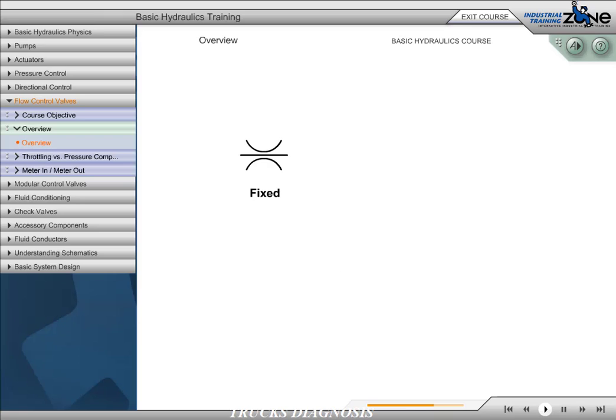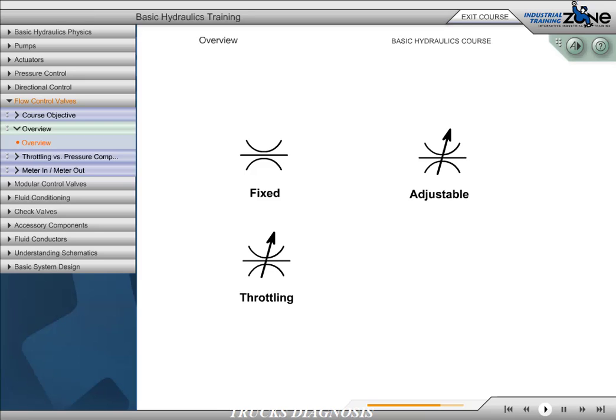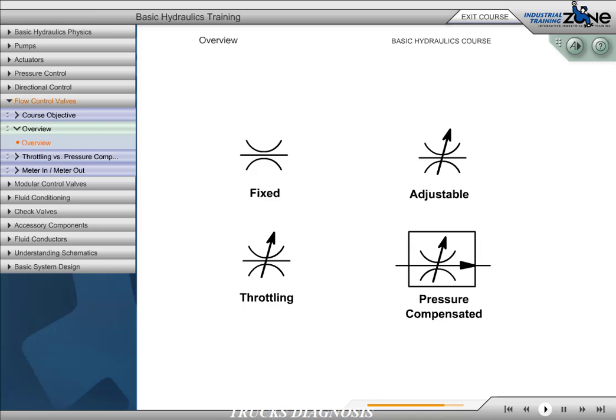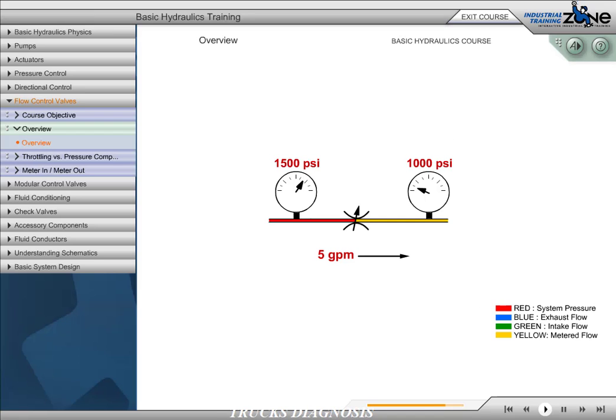Flow control valves may be fixed or non-adjustable, or adjustable. In addition, they may also be classified as throttling only or pressure compensated. The amount of flow through an orifice will remain constant as long as the pressure differential across the orifice does not change. When the pressure differential changes, the flow changes. A change in load or upstream pressure will change the pressure drop across the valve.